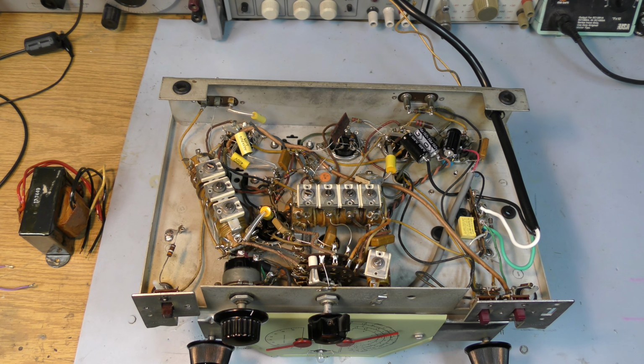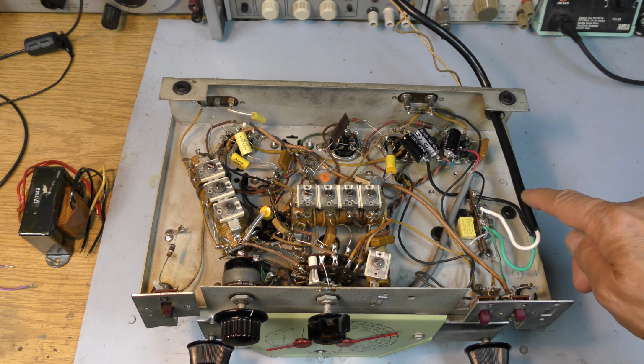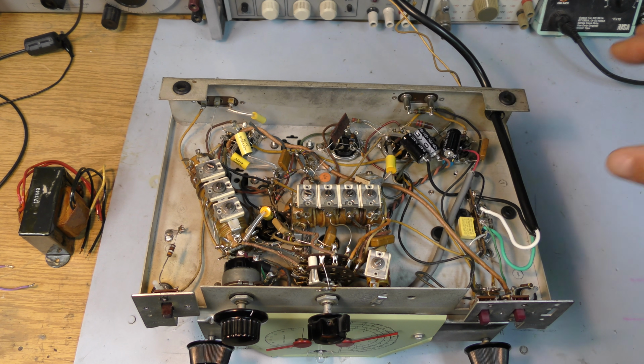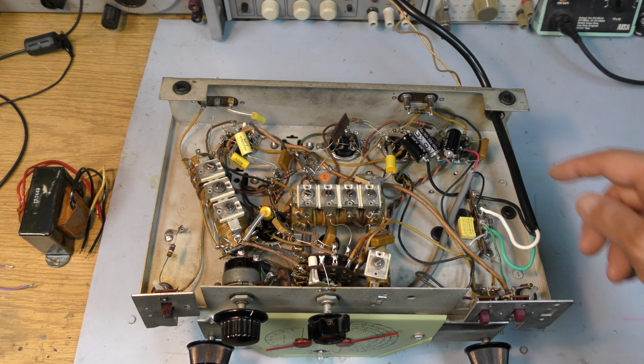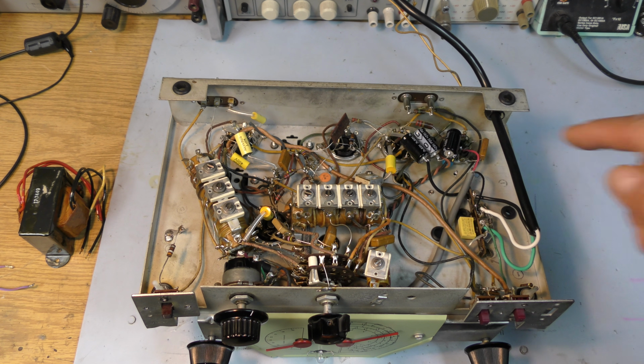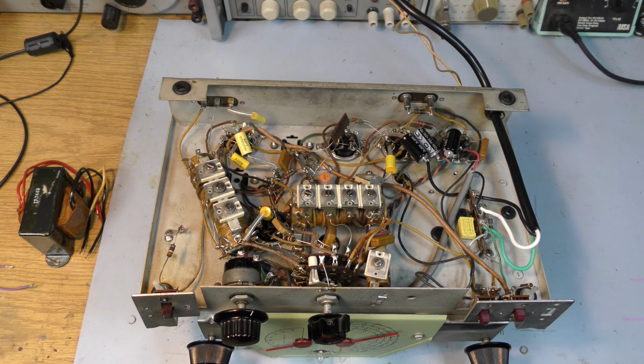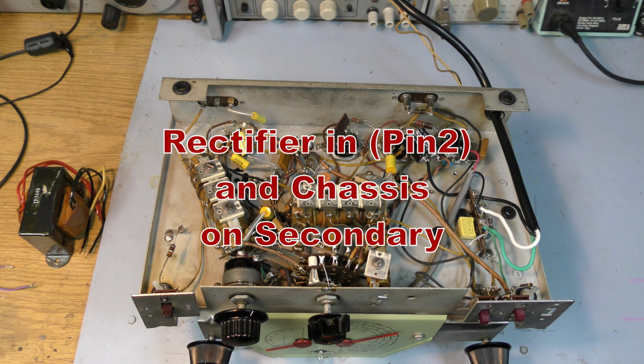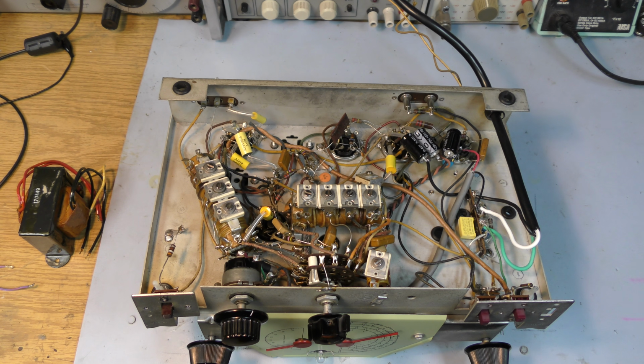So how to wire the transformer in line? On the line side, with power coming in, we have our fuses, we have our safety caps. We also want to have our switch involved. So the switch, the safety caps, and the fuses are all on the primary side of the isolation transformer, so we're breaking the neutral connection. The neutral connection on this side goes to the primary. The neutral connection on the other side goes right to the inner chassis, so that's the secondary of the transformer. You're going to pin 2, the input of the rectifier, and directly to the inner chassis. That's your secondary windings on your isolation transformer. That way, all of the protection devices are on the primary side of the transformer, thus protecting everything downstream.